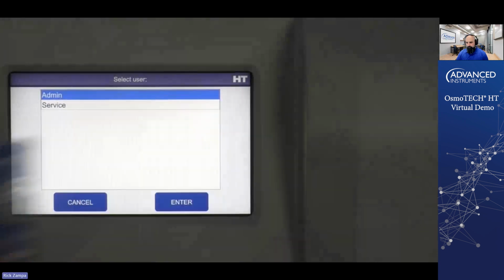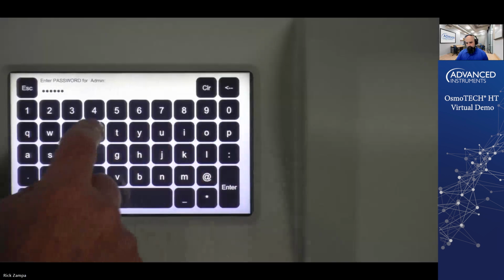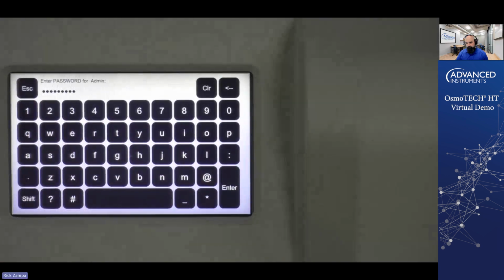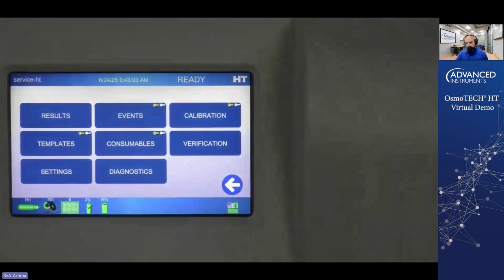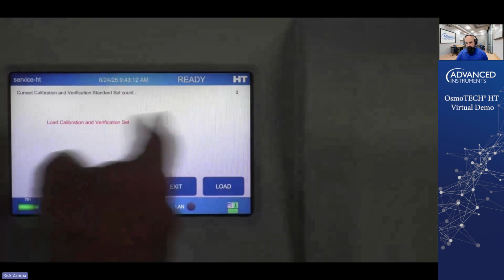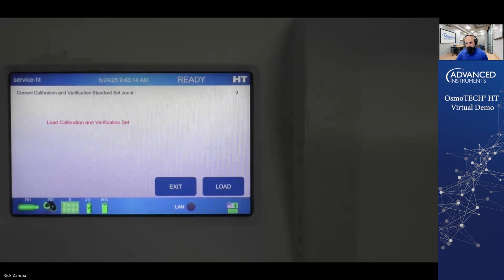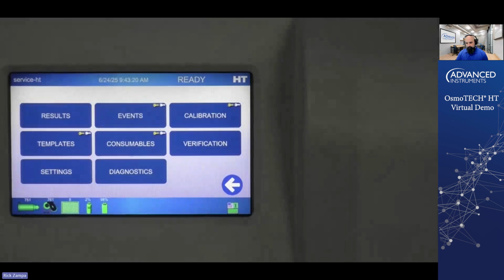Calibration, as I mentioned, comes with the calibration cassette here. This is your calibration cassette. You would enter into the calibration function. It's then going to walk us through a couple of steps. We then start the calibration and then we run the calibration. So it's load calibration and verification set. I would do that and then start the test. Great thing about the system is I can exit out of here. I have not made any changes to the system or changed the calibration functionality. It maintains its old calibration until it says calibration complete and then updates the data from there.